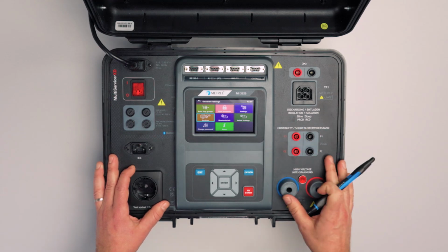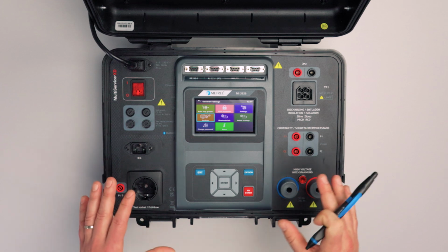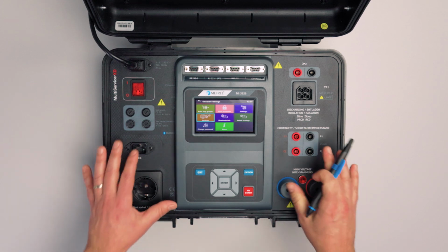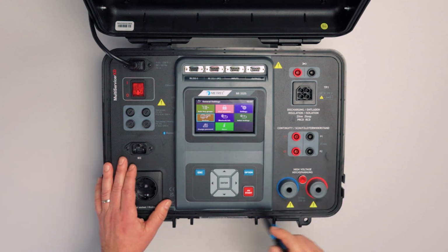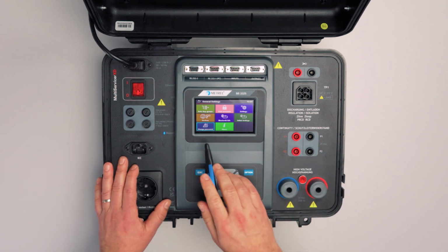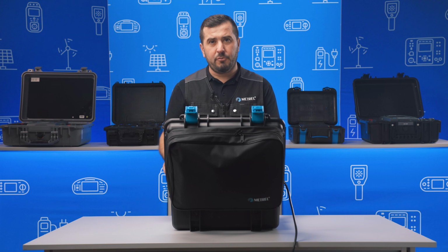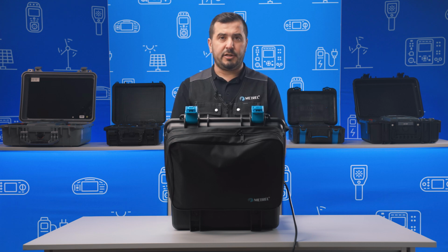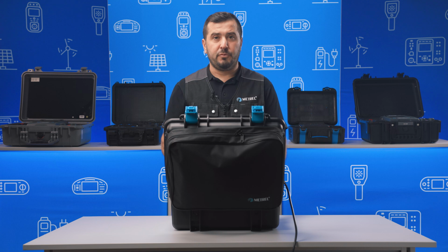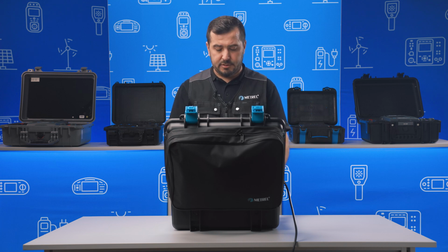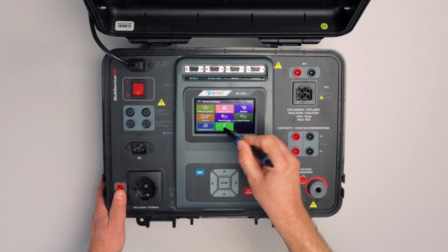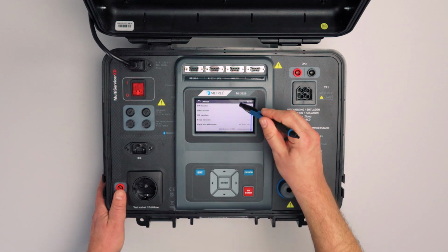Then the next one is the initial setting itself. This will basically mean that the instrument will be set back to the factory settings. Change password menu serves for changing of the high voltage password. The instrument has the functionality that before we want to start the high voltage test, the instrument always requires the high voltage password, so only the users that know this password can start the high voltage test. The last one in this group is the About menu.